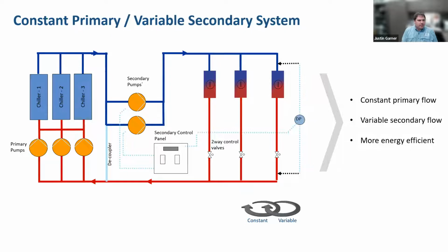With the advent of variable speed drives, we then started to see variable secondary systems, such as this one, whereby in many cases it was still constant speed primary pumps. And most of the time they would be matched to the chiller or boiler. And then you obviously have to have a decoupler there so that you can decouple the primary loop from the secondary loop. But what was nice about this setup was that you could match your secondary flow to the load and remove, in most cases, your bypasses.